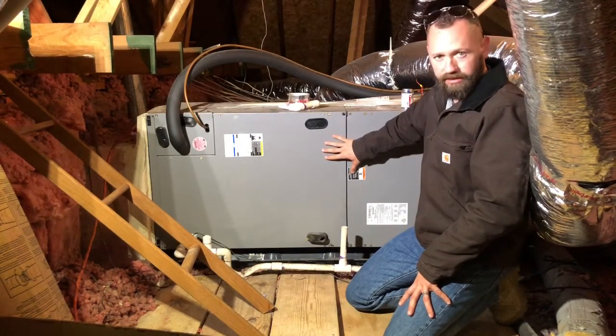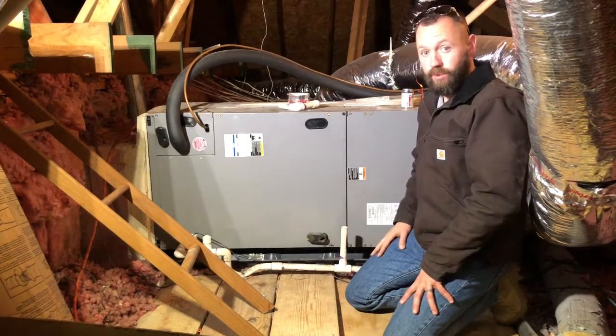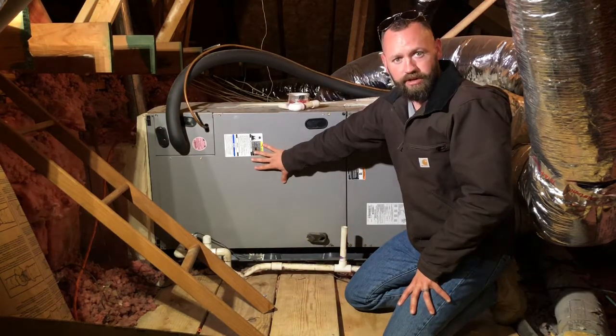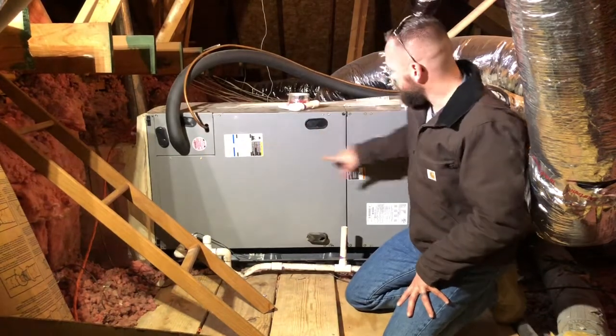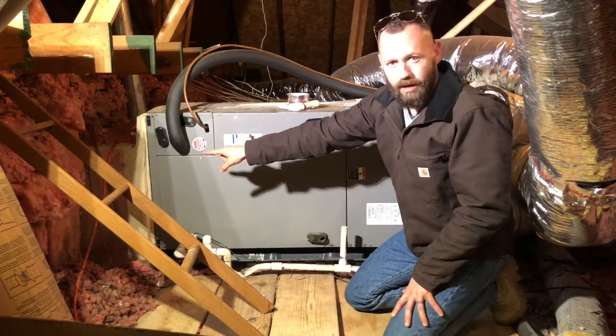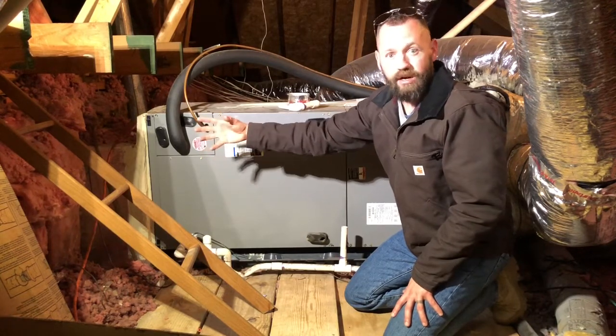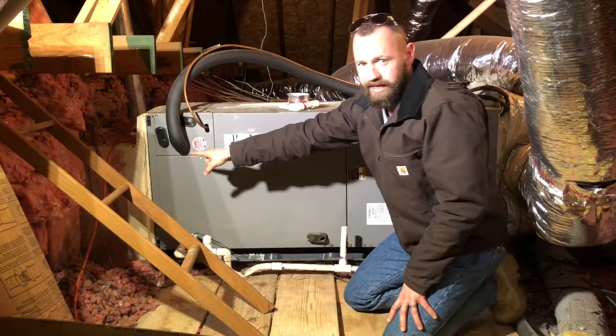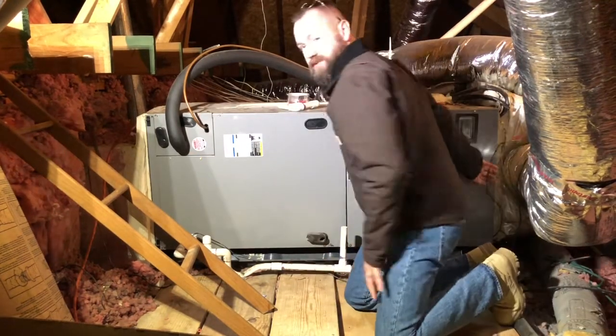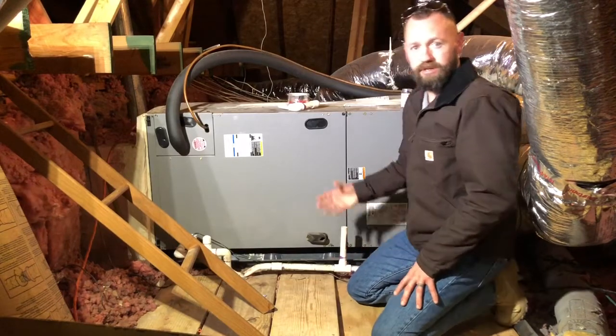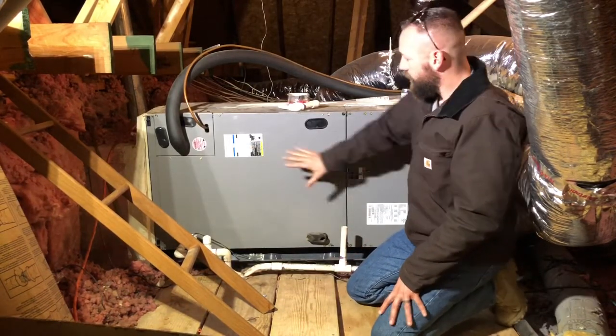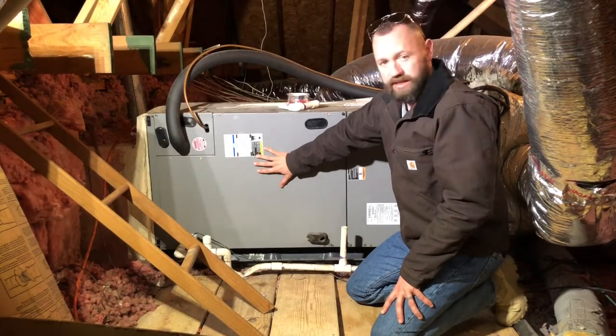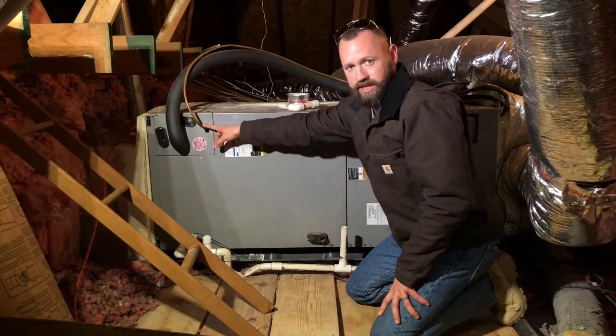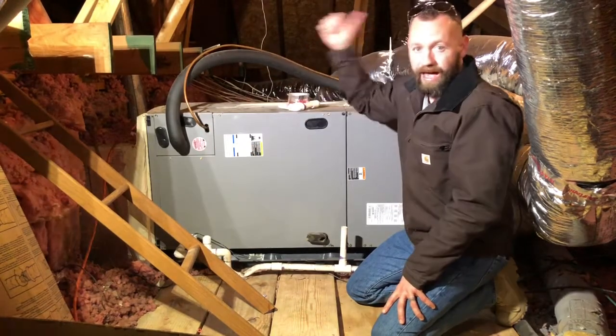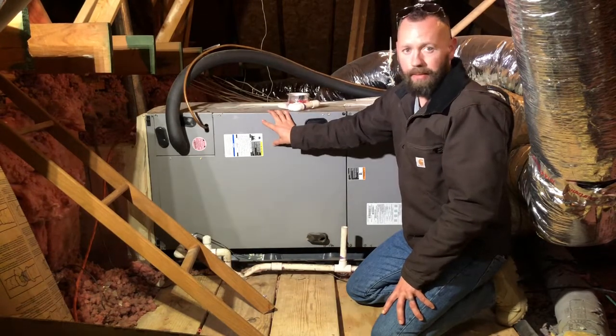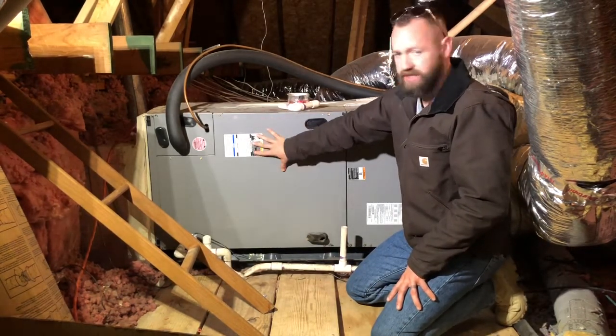Now inside this air handler, we have three different components. The first one is the evaporator coil for your air conditioner. Now on this unit, it goes left to right. So we have our return air coming into the unit on the left side, and that's air returning from the home to the unit. It goes through the unit, and then behind me is the supply air plenum. That's where the air is supplied to the home. So this is left to right. On this left side is the evaporator coil. We can tell based on this copper. This copper here connects this evaporator coil to the outdoor unit, which is a condenser coil. They operate together to cool the home. So this is the evaporator coil.